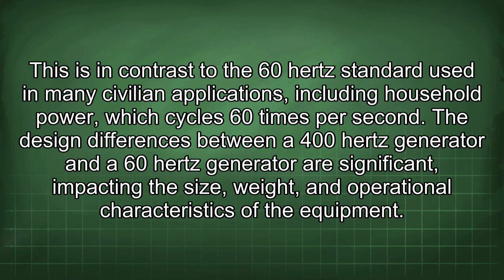This is in contrast to the 60 Hz standard used in many civilian applications, including household power, which cycles 60 times per second. The design differences between a 400 Hz generator and a 60 Hz generator are significant, impacting the size, weight, and operational characteristics of the equipment.